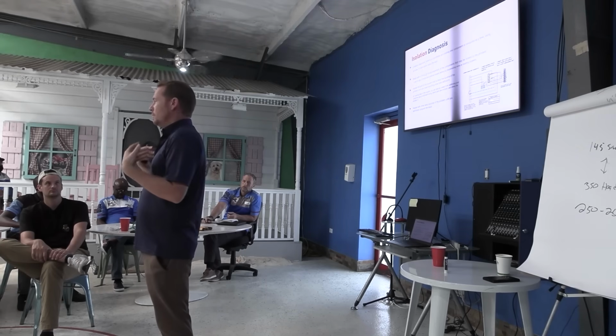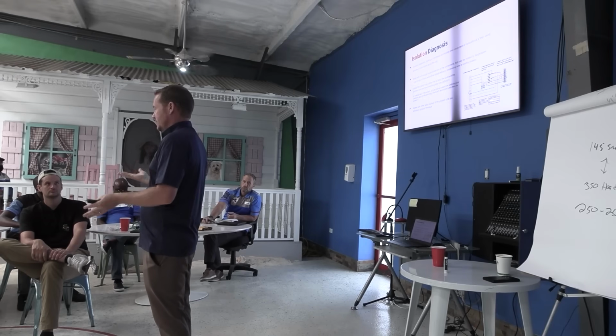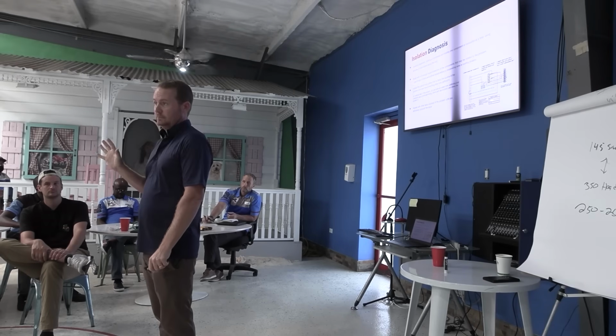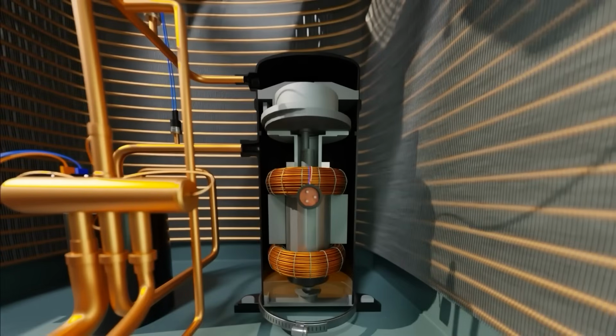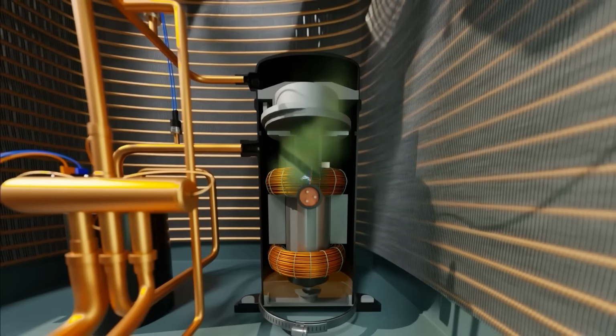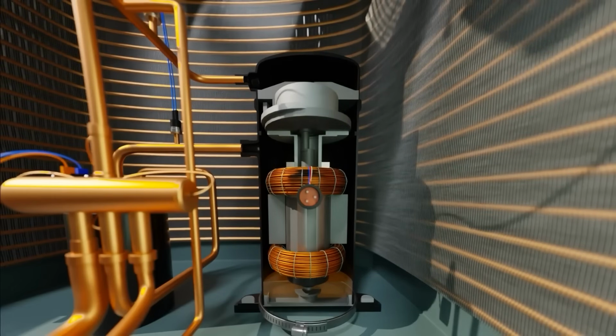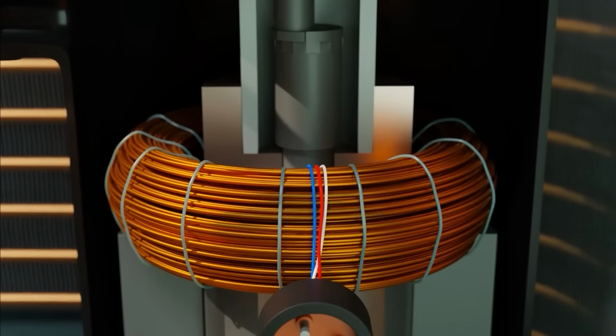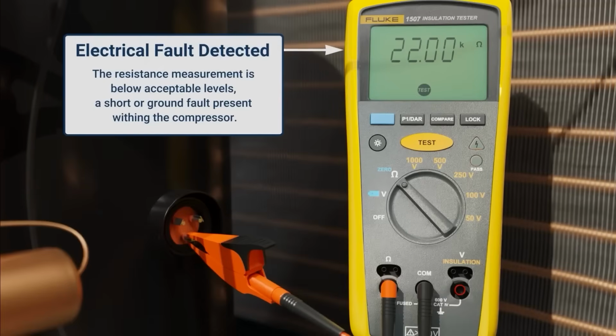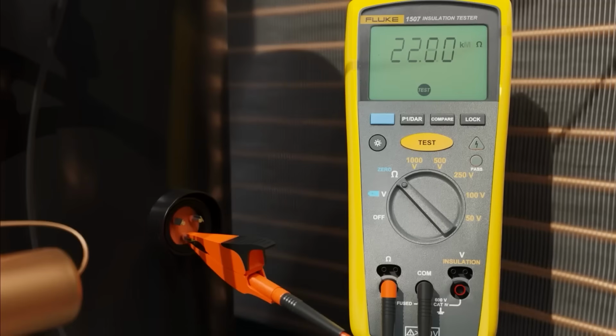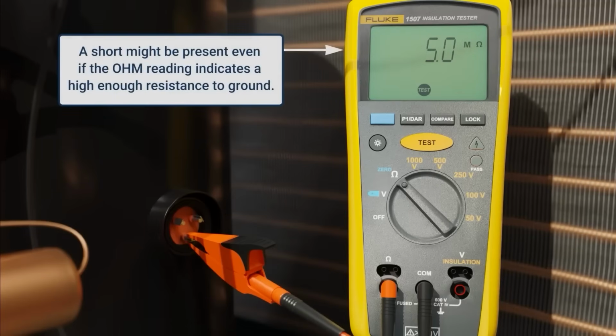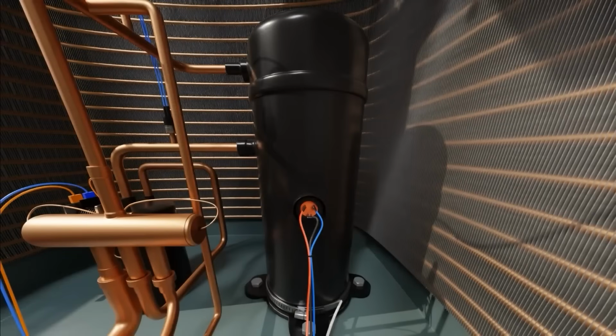In electrical work, this is really handy. I'll give you one of the most common examples. You have a compressor you're convinced is shorted, a grounded compressor. Everybody's seen that before. You knew it was grounded because the breaker tripped, you reset it and it tripped again, and you ohmed out the compressor to ground and said, okay, I'm convinced this is shorted. But sometimes it's not that straightforward.